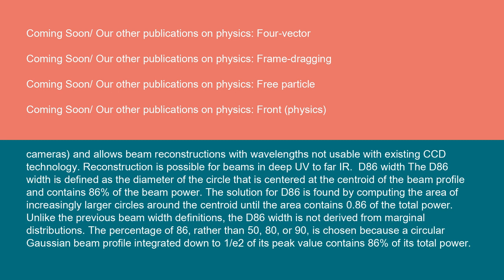D86 width: The D86 width is defined as the diameter of the circle that is centered at the centroid of the beam profile and contains 86% of the beam power. The solution for D86 is found by computing the area of increasingly larger circles around the centroid until the area contains 0.86 of the total power. Unlike the previous beam width definitions, the D86 width is not derived from marginal distributions. The percentage of 86 rather than 50, 80, or 90 is chosen because a circular Gaussian beam profile integrated down to 1/e² of its peak value contains 86% of its total power.